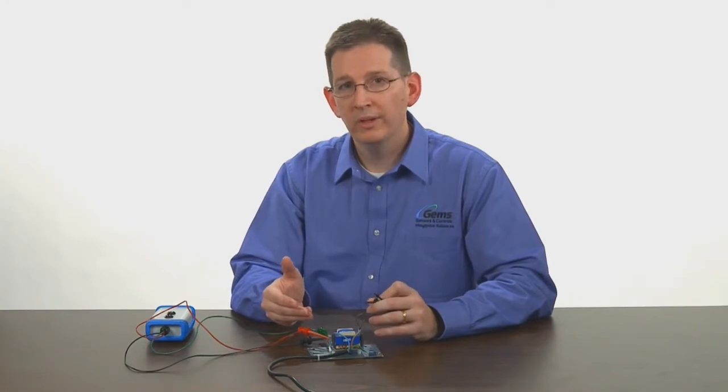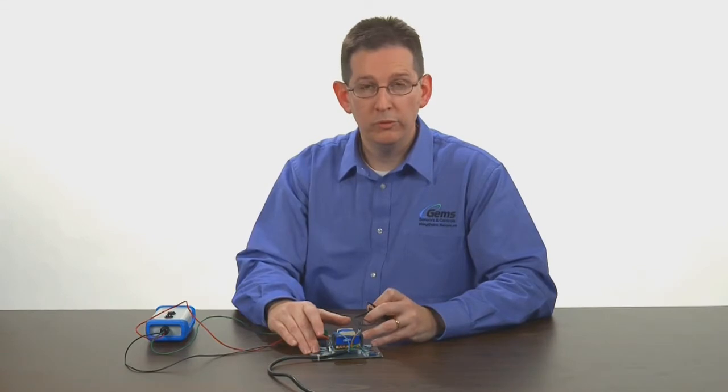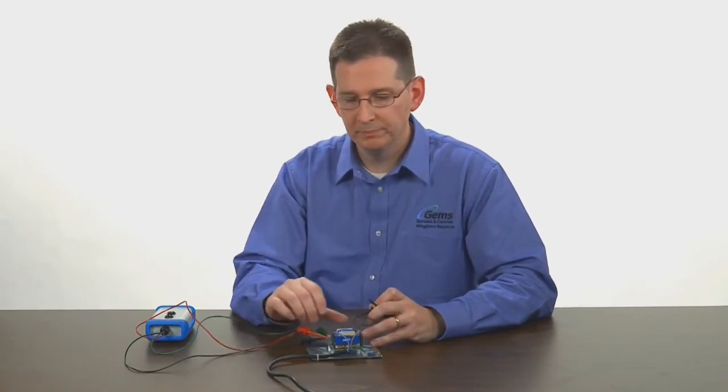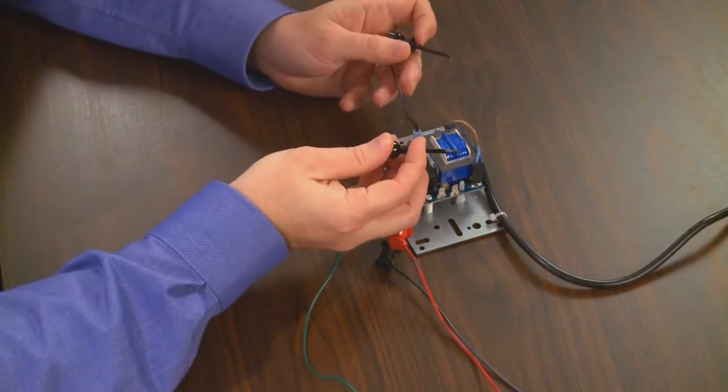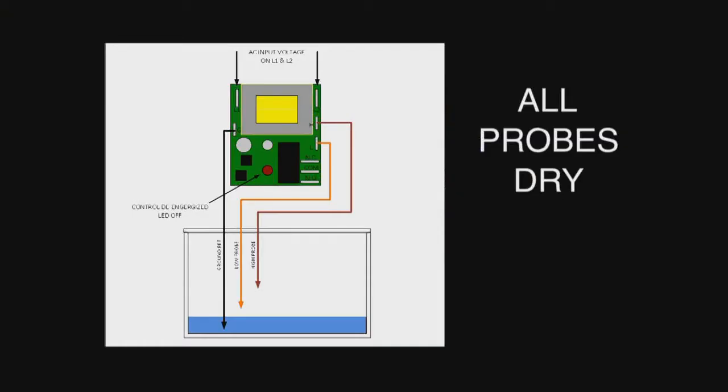The direct mode indicates that it will operate when probes become wet and de-energize when probes are dry. To do this we bring in our AC power to the two line voltages and we use a series of jumpers to simulate either single level service or differential service.